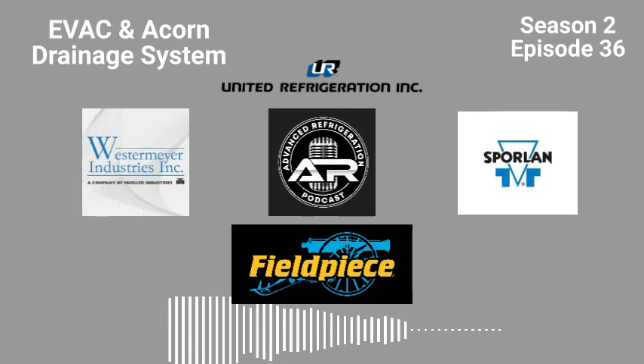The only other thing that I can tell you, if you have a clog in some of these, you can do what's called a power flush. I used to have a ball, one of those rubber balls, I don't know if they call them pickleballs, on a piece of rope. I would drop it down behind the case, and I had at least 2 of them, and I was able to drop those balls directly over the ports that they have open for the vent, and then hit the accumulator button, and then all of a sudden you have a greater vacuum, because now it's not trying to suck any air from the ambient.